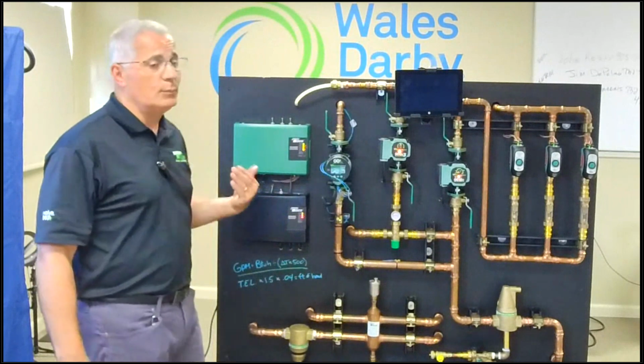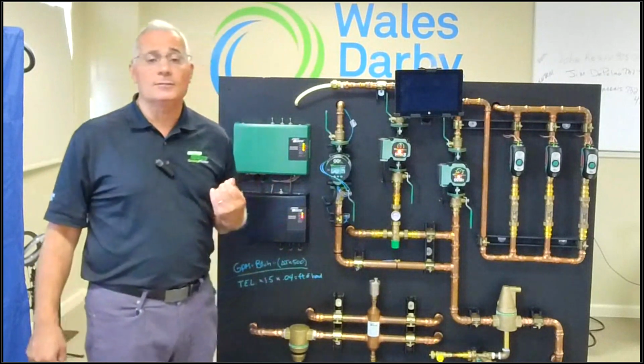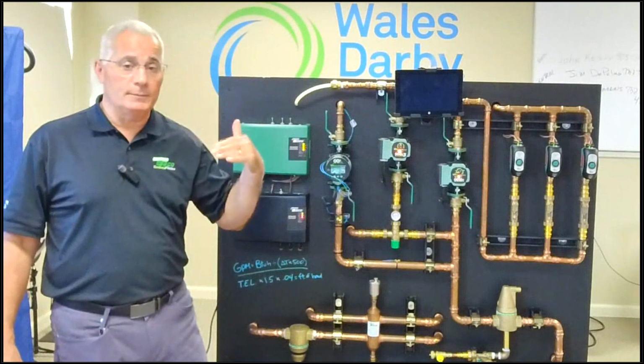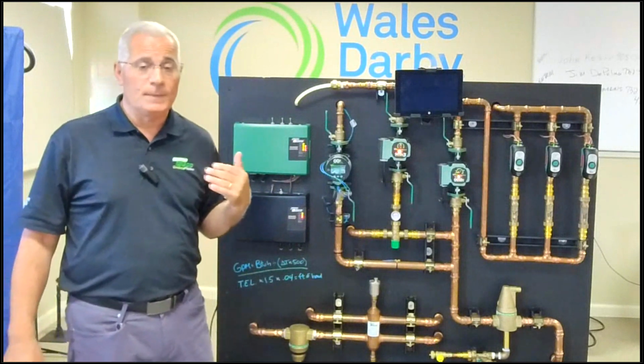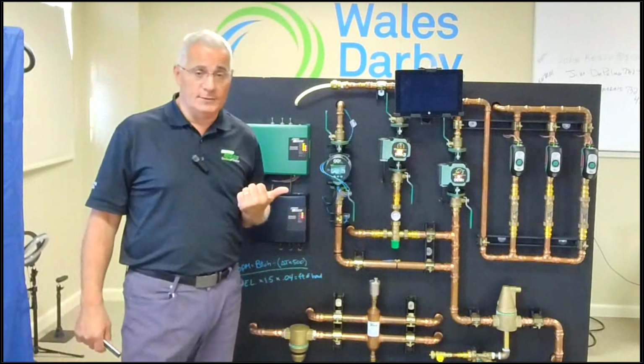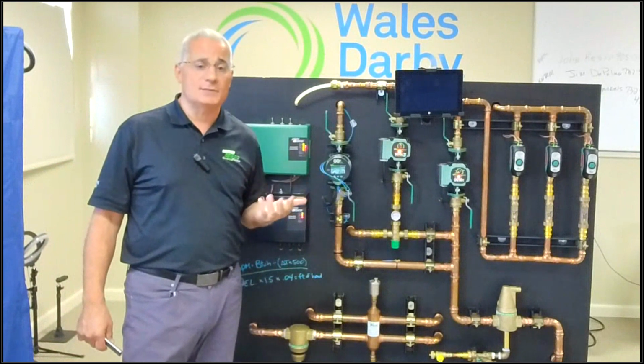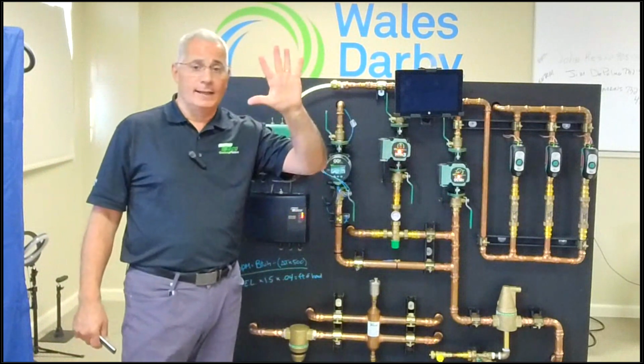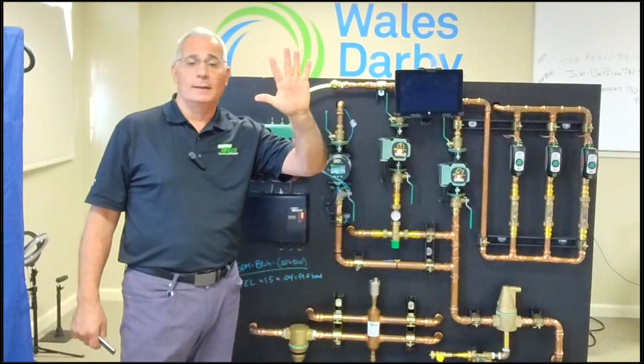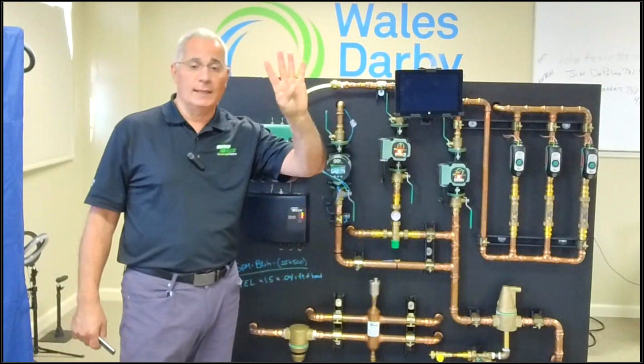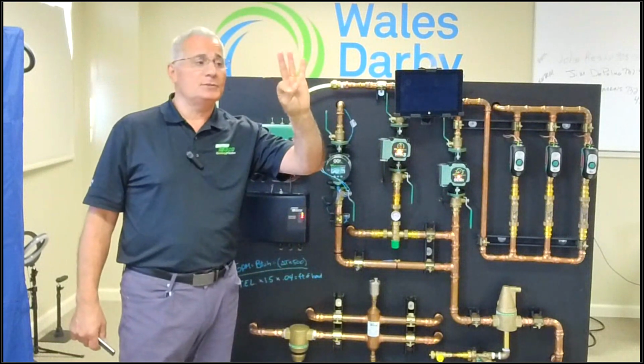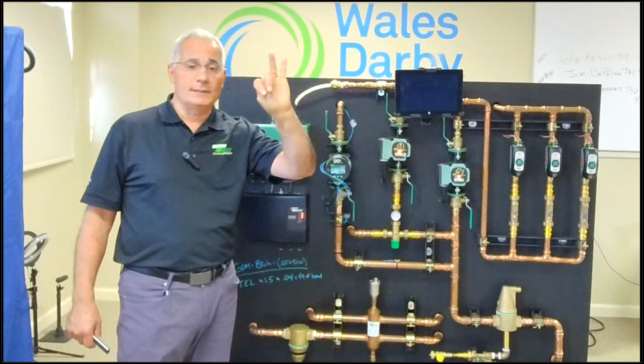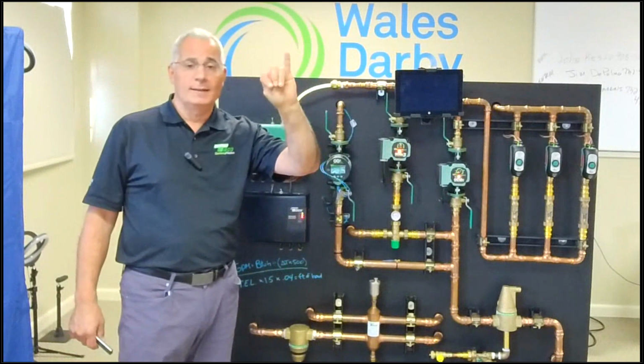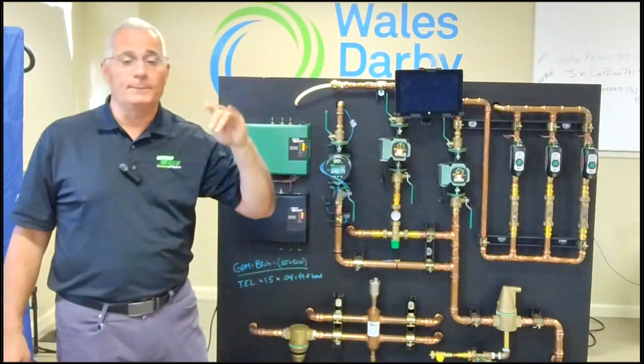Your condensing boiler is going to be set to a heating curve, and it will be changing its output based on outdoor air temperature. So right there, that is an energy saving feature because I am saving on fuel. All right, I don't have to fire all at 100%. You know, I may only have to fire at that much or that much, that much. Maybe we're down to maybe 25%, and maybe we're down to its lowest firing.